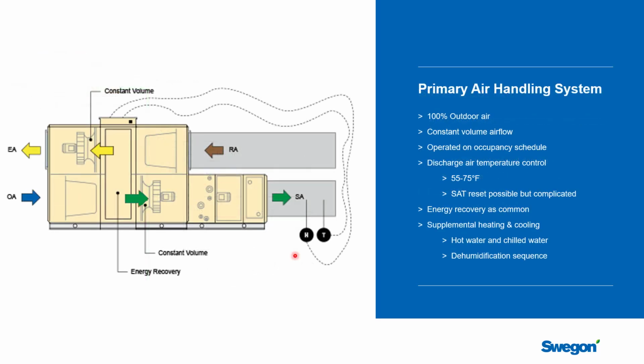So let's talk a little bit more about the air handling unit itself and its controls. So we said it was a constant volume system, so there's no adjustment to the airflow. That would be done during commissioning, and so unless there's a change in the design of the building, it will be either off or providing a constant airflow. Now, in a lot of chilled beam projects, you have some form of energy recovery unit, and in this case, this is a 100% outside air arrangement.